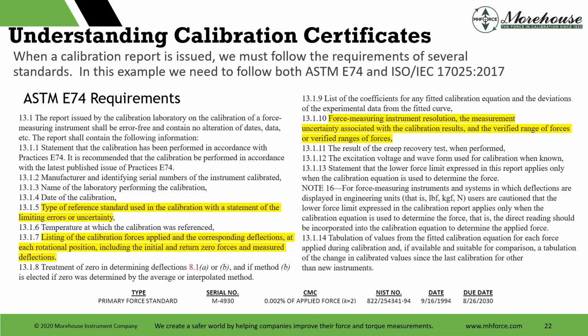And then we're talking about E74. So E74, we have to follow ISO 17025 guidelines. We also have to follow E74 guidelines on the calibration certificate. So here's some that, manufacturer identified, serial numbers, a lot of them overlap, but here there are some other things that may not overlap. And is the type of reference standard used in the calibration with a statement of the limiting errors or uncertainty. Listing of the calibration forces applied and the corresponding deflections at each rotational position, including the initial and return zero forces and measured deflections. 13.1.10, force measuring instrument resolution, the measurement uncertainty associated with the calibration results, and verified range of forces. So that's another thing.